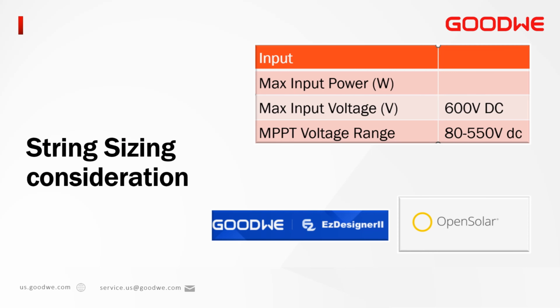Although string sizing isn't part of the installation and commissioning, I do want to point out the different tools available for the design. We recommend that you always check the maximum string sizing with our EZDesigner to ensure that the inverter will operate at peak efficiency during the range of temperatures of the site. Note the MPPT voltage range of this model: you need to design the system to ensure you are targeting the maximum voltage and minimum within this range. Outside the MPPT voltage range, the inverter is not at its peak efficiency. In addition to our EZDesigner, we also work with most of the modeling tools such as OpenSolar and others.